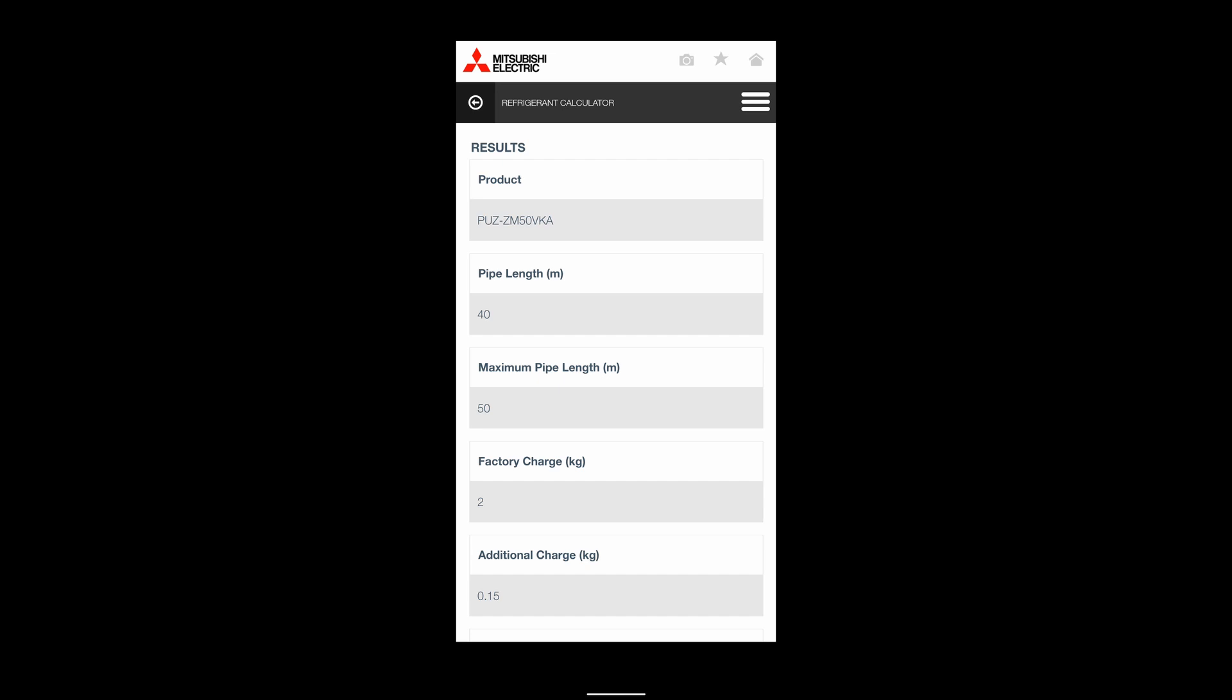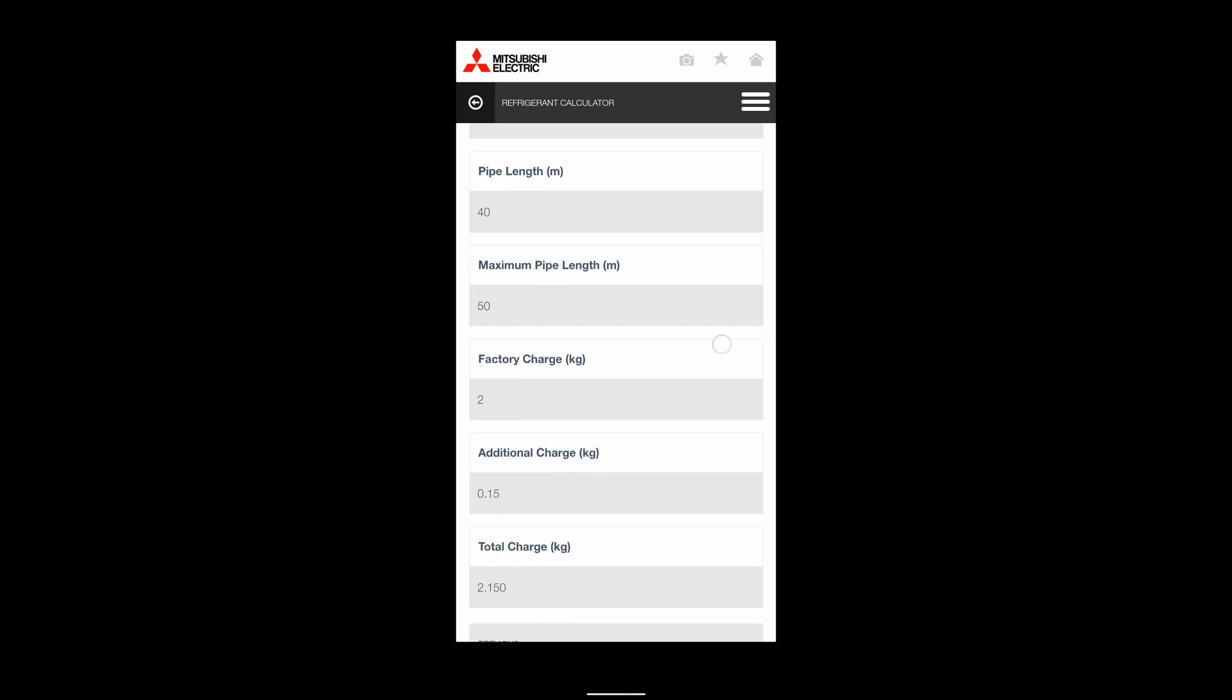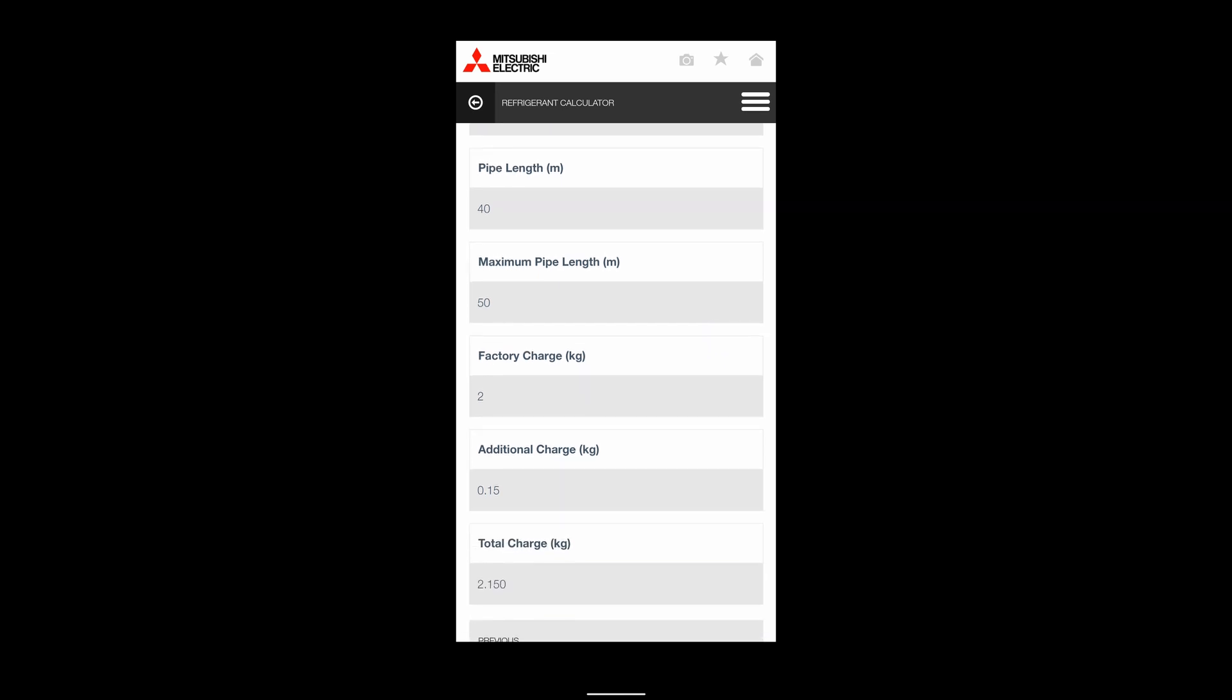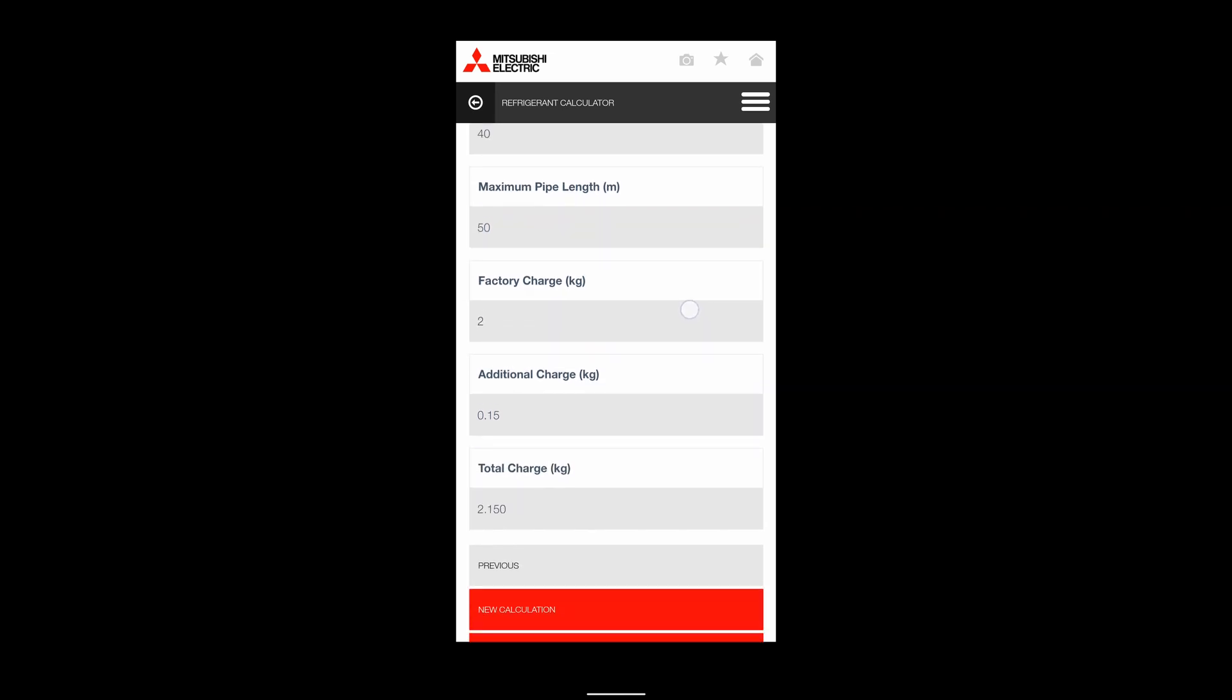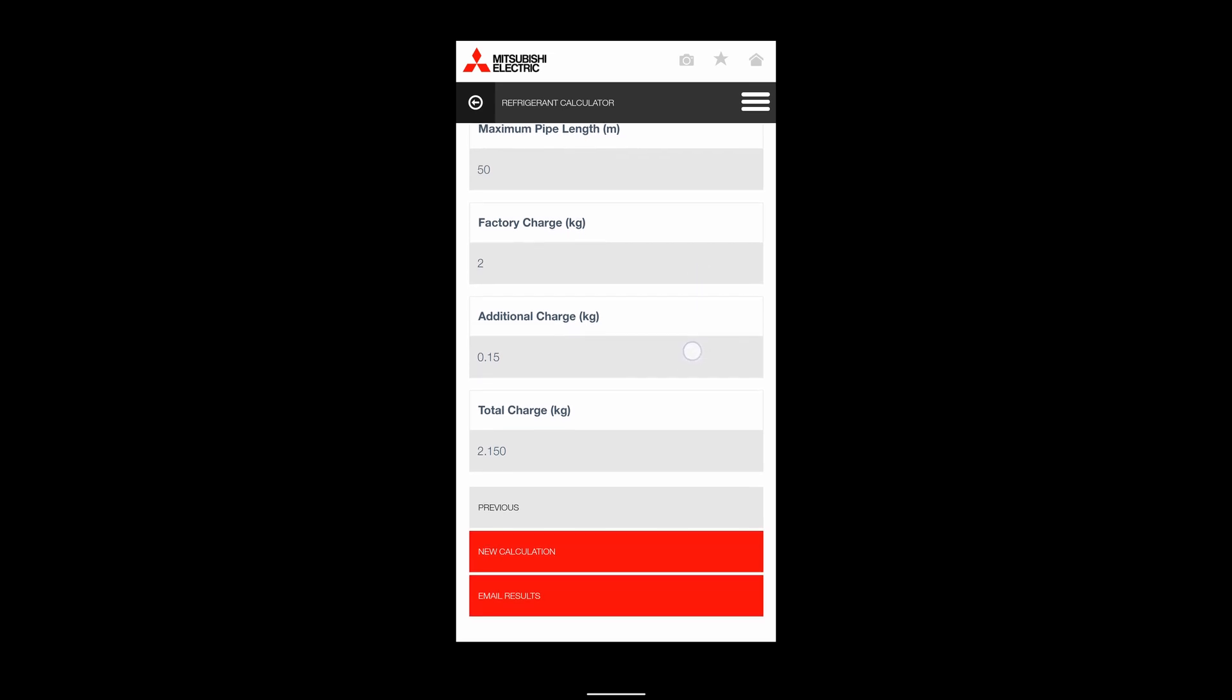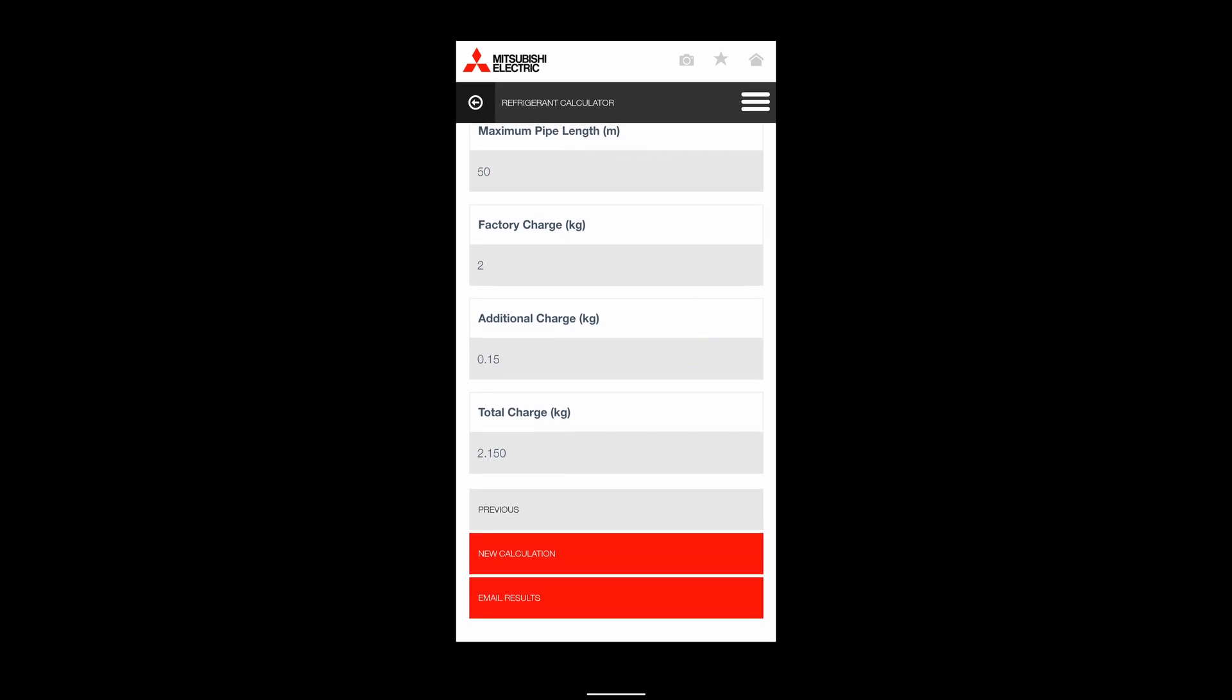There we go - it tells me the maximum is 50 meters. Factory charge is two kilos. The additional charge I require is going to be 0.15 of a kilo.